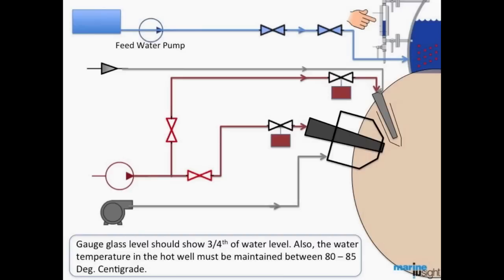Check the water level in the boiler drum through the gauge glass. The gauge glass level should show three-fourths of the water level. Also the water temperature in the hot well must be maintained between 80 to 85 degrees centigrade.